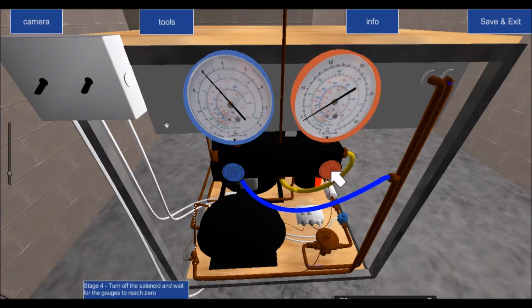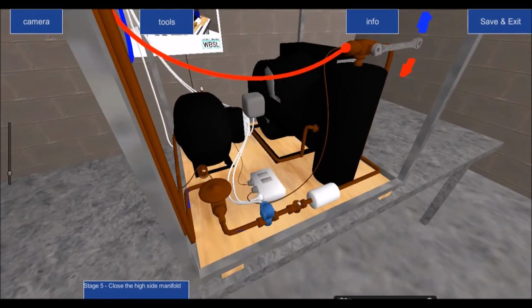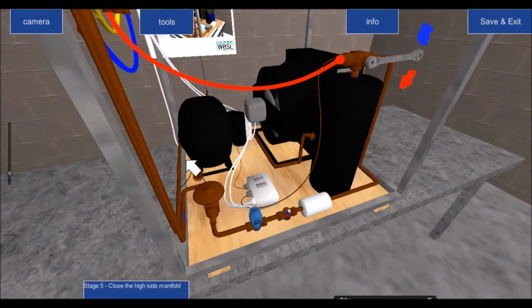Now I haven't closed this and I haven't closed this. I've left these in the open position. As soon as I knock off my solenoid, no more refrigerant is allowed to go past the solenoid valve, and you can see that all the refrigerant on the low side is being sucked out of the low side and pushed back into the compressor. The compressor pushes it to the high side of the system, and the liquid refrigerant will only go as far as the inlet of the solenoid, which is this point here, right? So it goes to this point here.